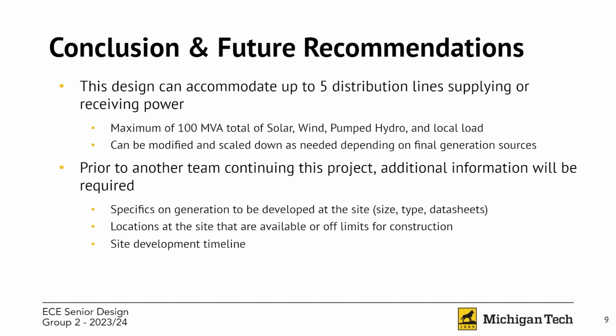In conclusion, this design can accommodate up to 5 distribution lines supplying or receiving power. We designed the project to be 100 MVA so that we can account for any future solar, wind, or pumped hydro. This project can be modified and scaled down as needed, as there are still some items that need to be addressed regarding which generation will be used and how big it will be on the site.